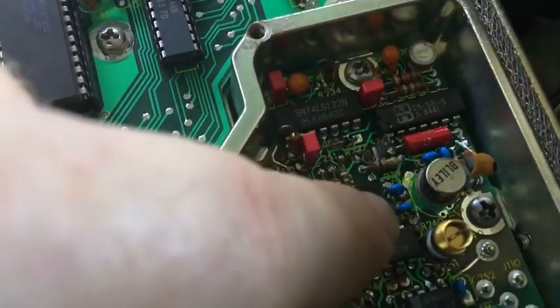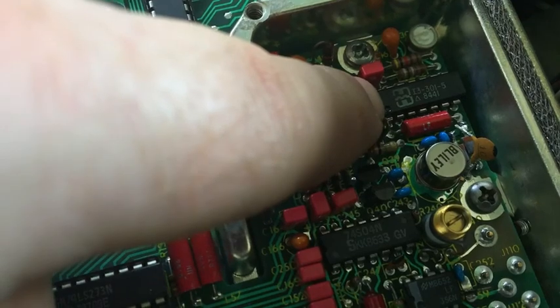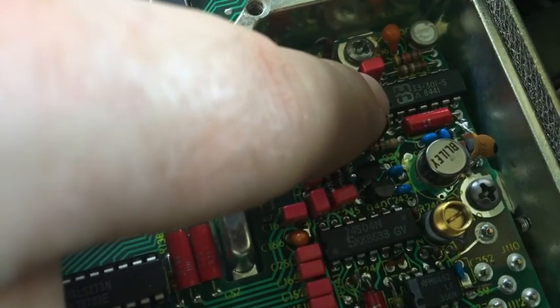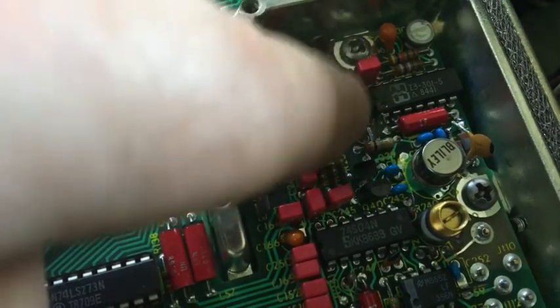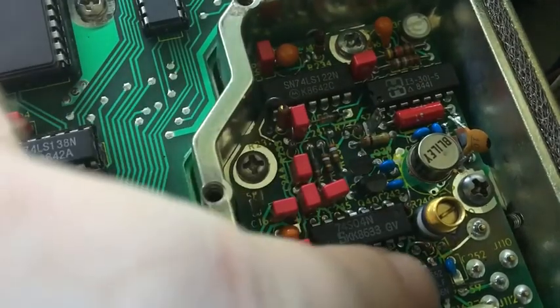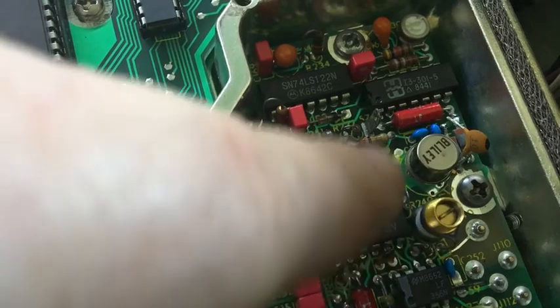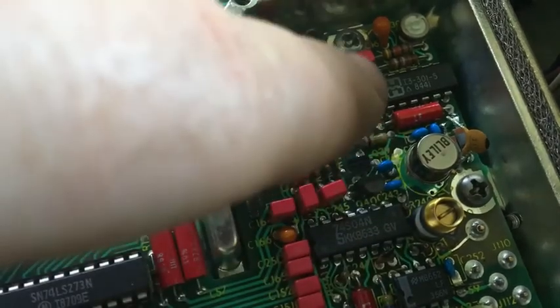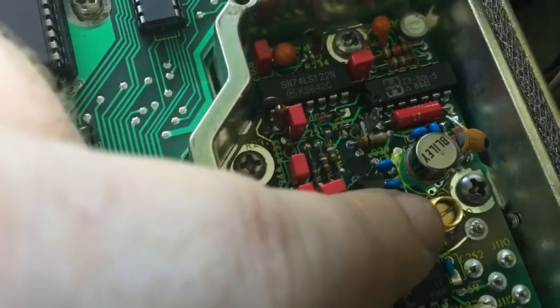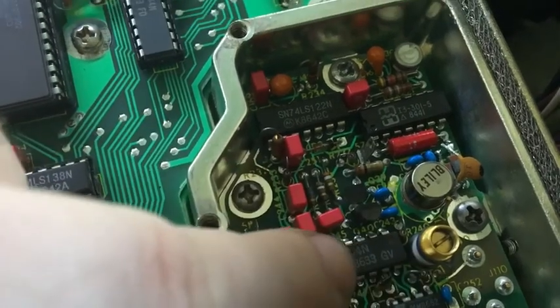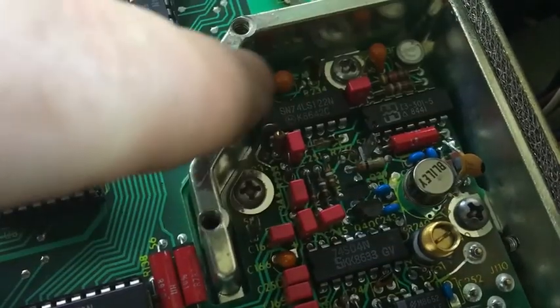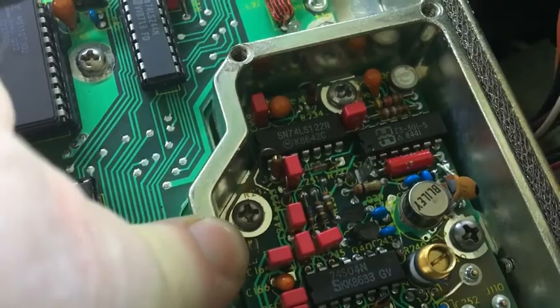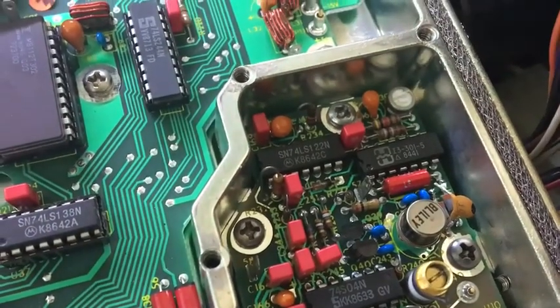So this is what controls the circuit here, this IC. I'm concerned that something is wrong in here, because based on the manual it should be locking frequency, then unlock again when you reach a certain adjustment, and that's not happening. So I'm going to have to look in this section really closely to figure out how this bit works, because this doesn't appear to be working correctly.